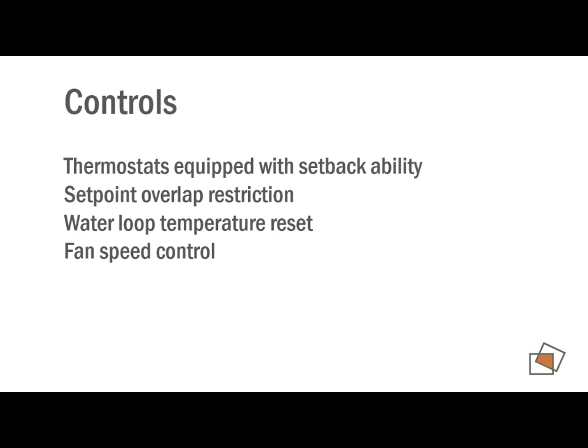If you have a water system, be it heat pumps or a hot or chilled water system, if you have a high heating demand, for example, the energy code wants you to be able to reset your hot water system temperature up, because everything's going to be more efficient if it has hotter water. You're trying to heat your building, you raise that water loop temperature, and everything's going to be able to perform more efficiently. Less equipment runs around those types of things. And then fan speed controls to be able to turn down fans and adjust those based on demand.